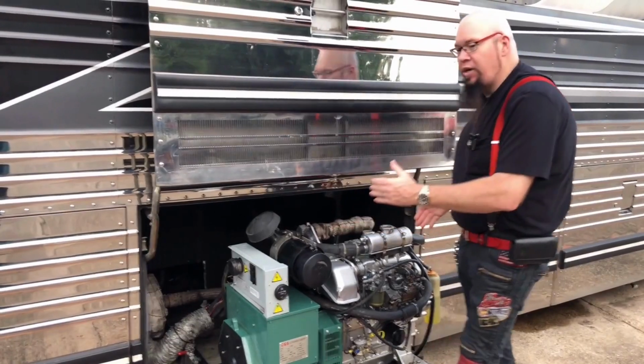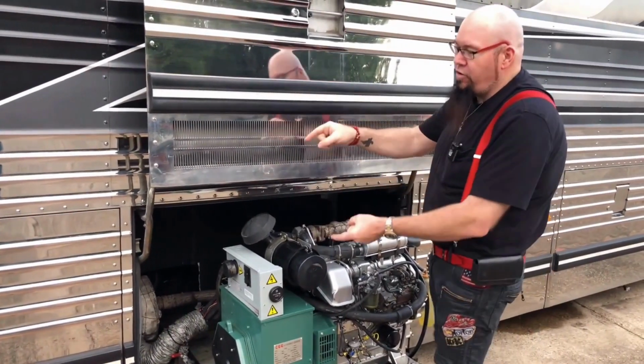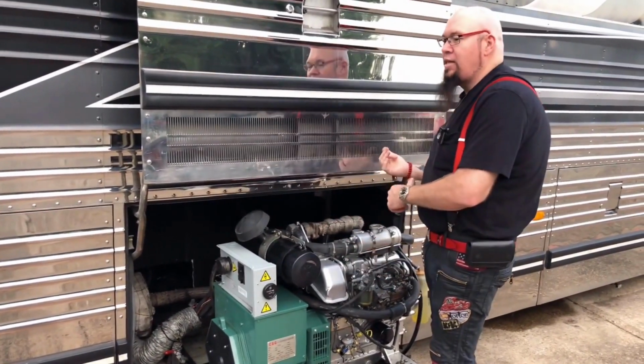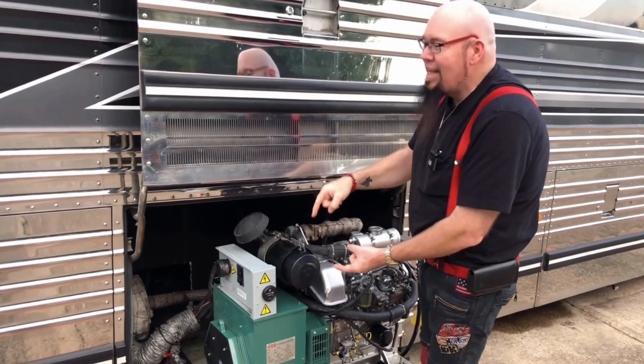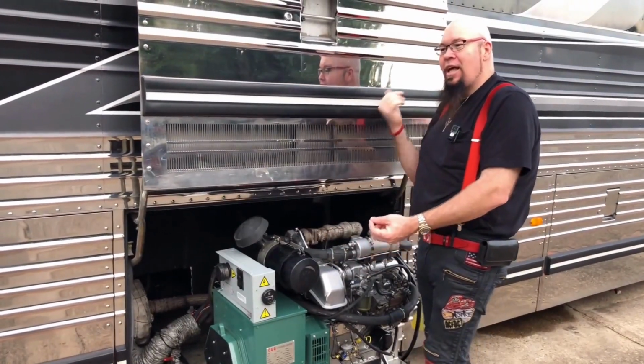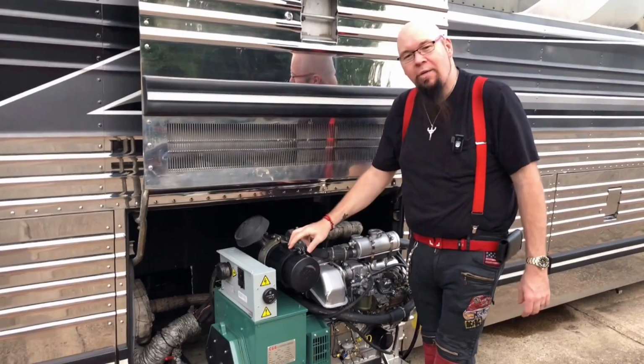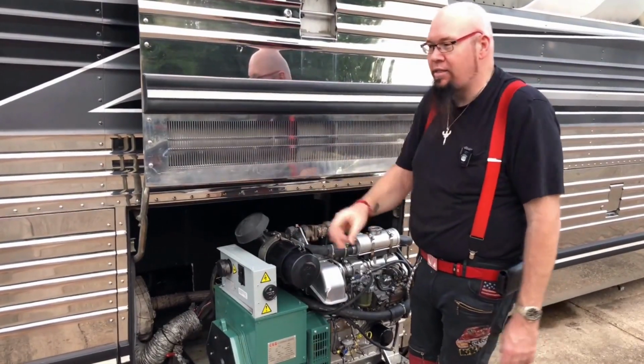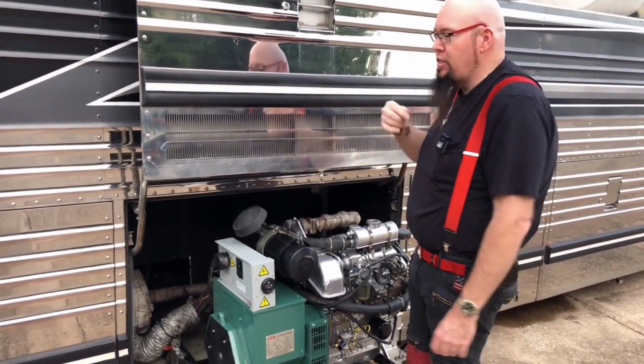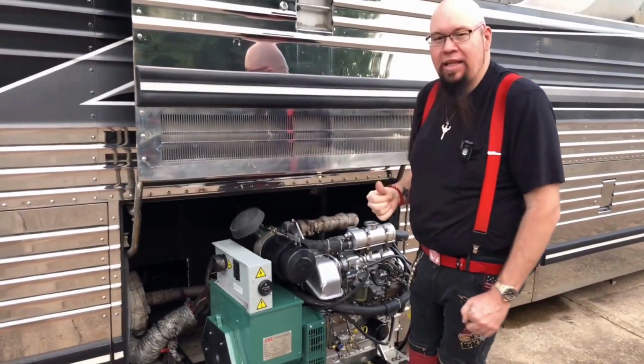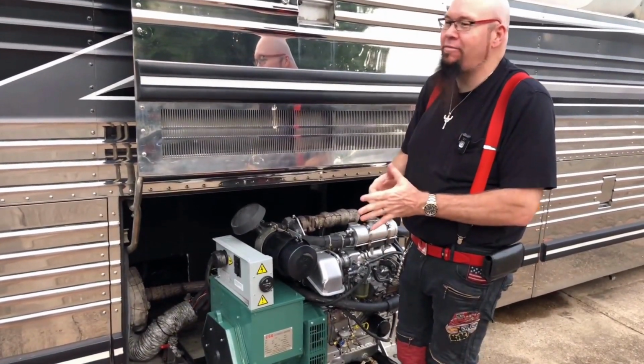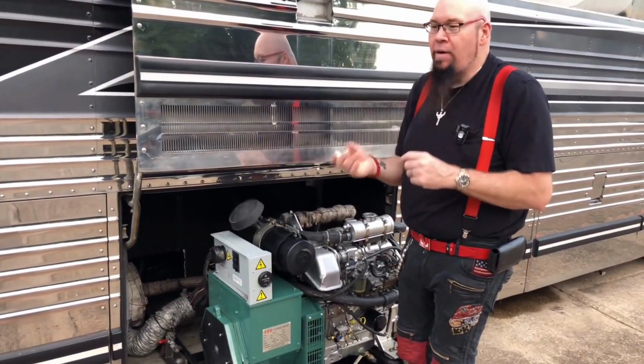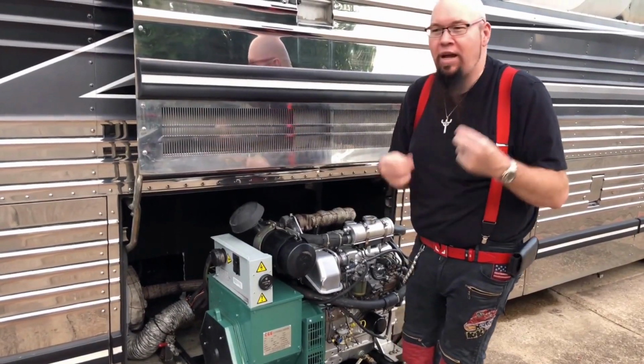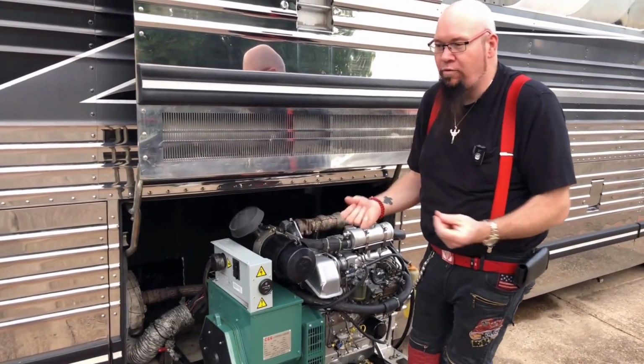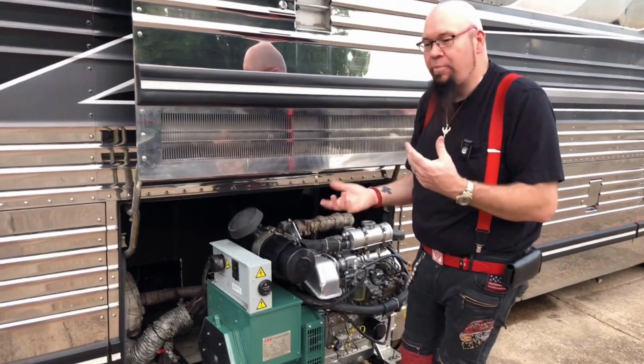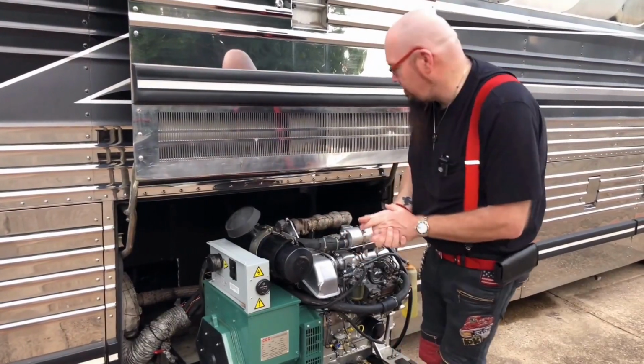The generator puts out power that the inverters use to charge the batteries to run themselves, and that runs all the electronics. However, the direct 220 coming off the generator runs your big appliances, like rooftop air conditioners, water heaters, stuff like that. Stuff that's not going to really be affected, you don't have to have a sine wave direct 120 or 240 volts for that. It can take a little up and down because it's just running motors and compressors.